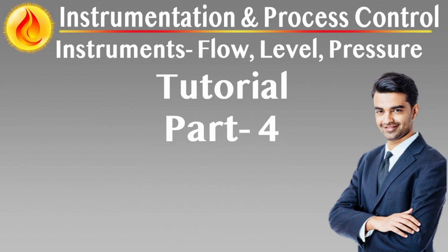They are the meter of choice in custody transfer, loading terminals, blending skids, and high viscosity liquid applications, where precision is critical and flow conditions are well controlled. Unlike inferential meters, PD meters do not rely on velocity or pressure drop. They physically count volume, making them ideal for applications requiring totalization, batching, or fiscal accountability.